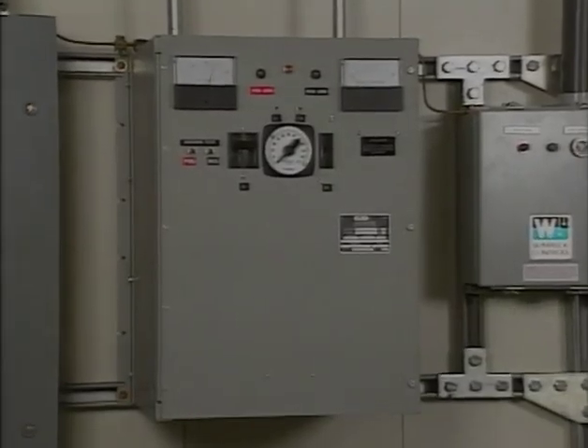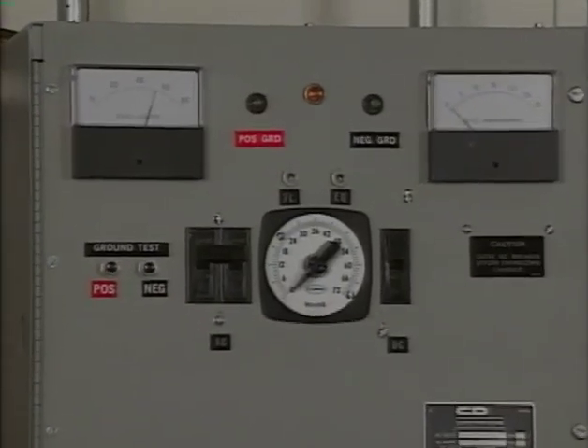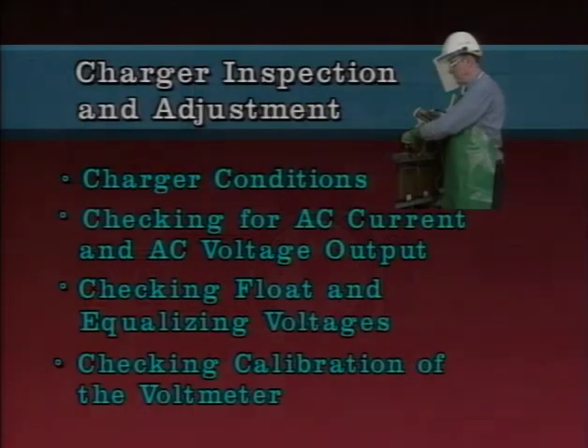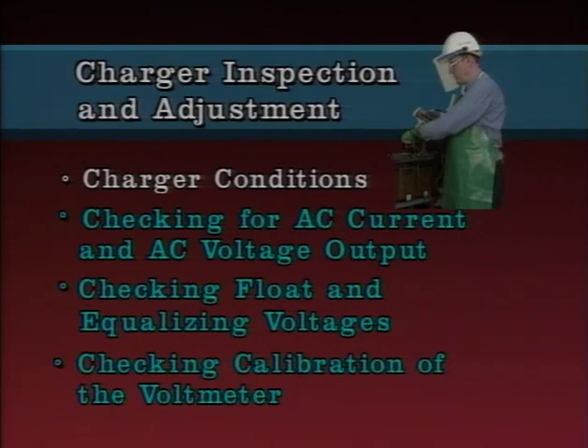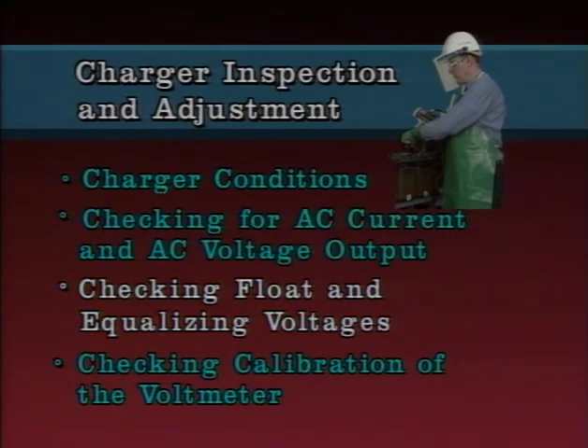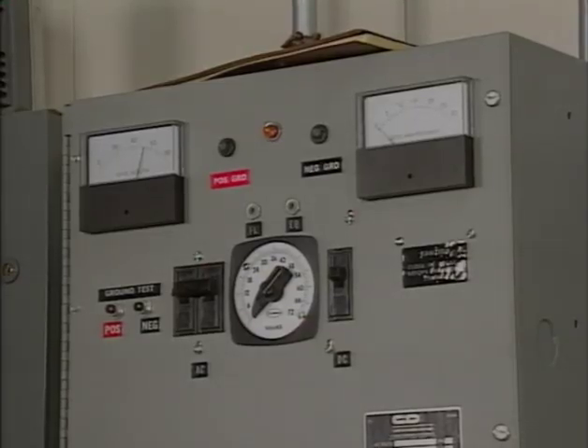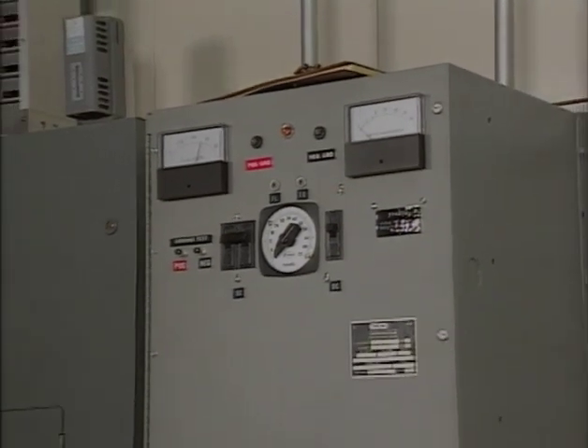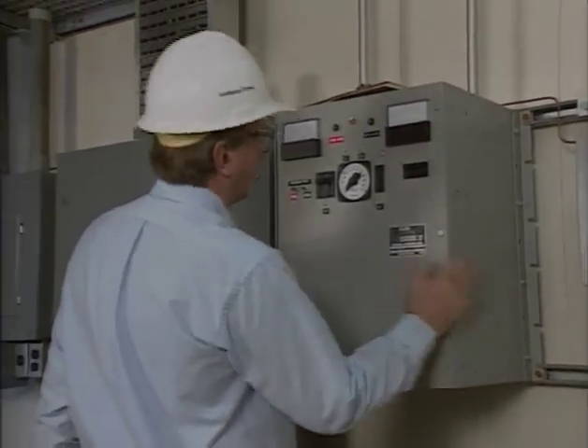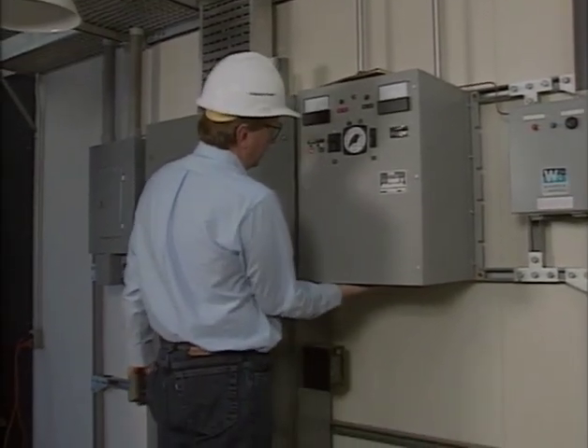All chargers require periodic inspection and adjustment. Proper maintenance will prolong the useful life of a charger and the battery that it serves. This last part of the program will demonstrate basic battery charger inspection and adjustment tasks, including inspecting general charger conditions, checking for AC current and voltage output, checking float and equalizing voltages, and checking the calibration of the charger's voltmeter. Routine charger inspections and adjustments are typically done while the charger remains in service, so internal terminals will be energized and all required safety precautions should be observed. A good place to begin is to check the charger for signs of excessive heat.